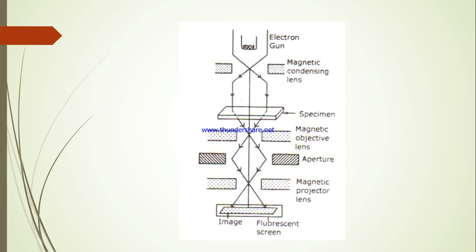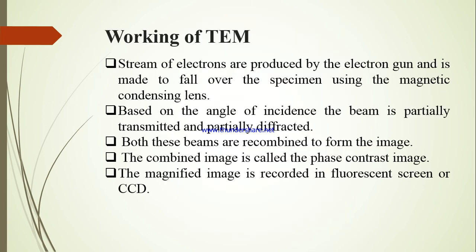Here there is no photomultiplier or CRO. The transmitted electrons are detected directly. There are no secondary electrons emitted from the sample, as in the scanning electron microscope. Here the electrons pass through the sample, and in such a way the images are obtained.